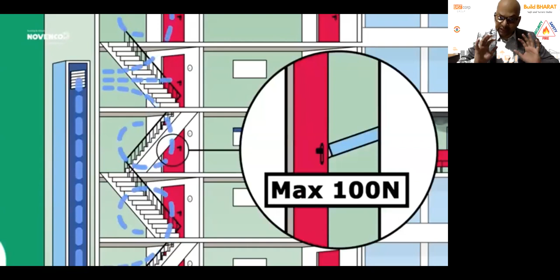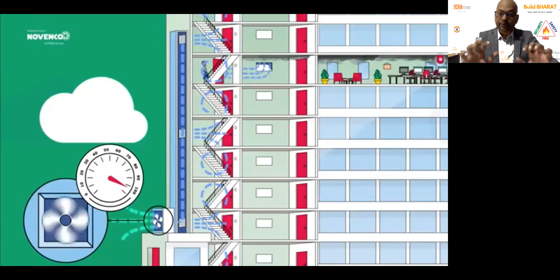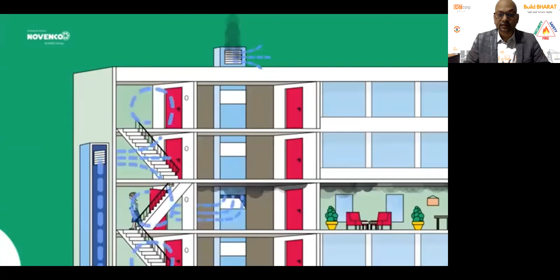The fire door is normally closed, but when you have pressurization, you should maintain that pressure in such a way that the door force is not more than 100 newtons. That's very important, because if you pressurize the other end too much, then you need a lot of force to open that door. So this is again an important element to test the system. The moment people start using the fire door, there will be some loss in air, loss in pressure. So you create the duct in such a way that it is going to compensate. At the same time, you create the differential fans in such a way that they will compensate that air. So the fans will start running at a higher CFM, so that the loss of air through the opening door gets compensated. And that's how you create that differential pressure constantly throughout the evacuation process.